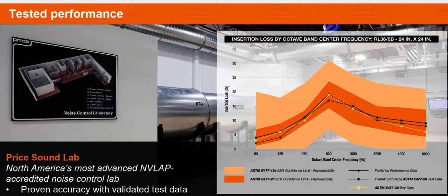So typically, when we have run into installed system effects issues, it's in ducted solutions, where all of a sudden the transition to the silencer is extremely drastic because they have a structural beam in the way, and the contractor had to work around it, and we didn't know. Then all of a sudden the back pressure quadruples. But for outdoor solutions, because we're trying to follow all these guidelines of big openings and low face velocity, we're pretty certain that we're not going to run into issues. And in the scenarios where we are not confident, we do suggest doing the next best thing, which is a CFD analysis, which is a good educated prediction.